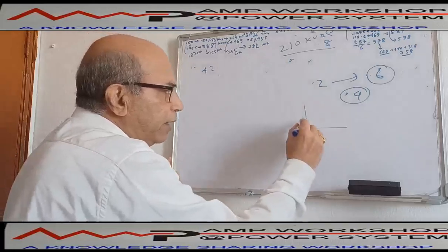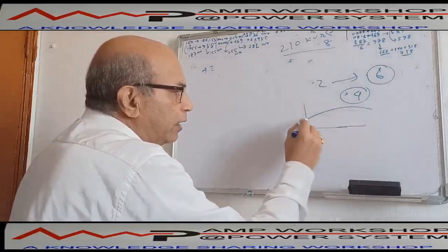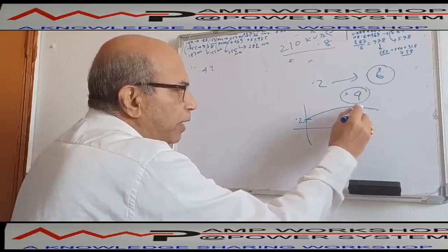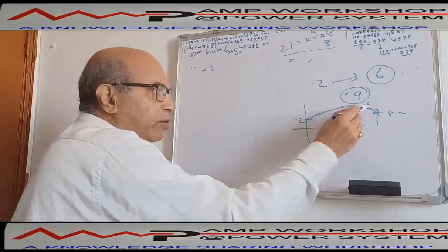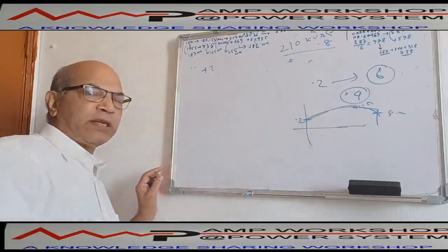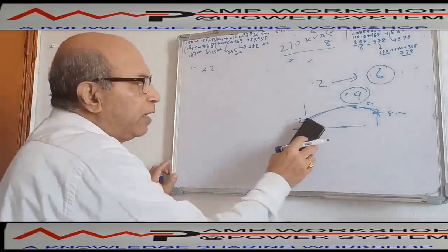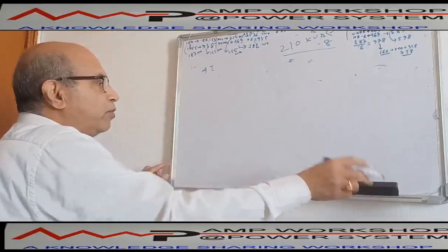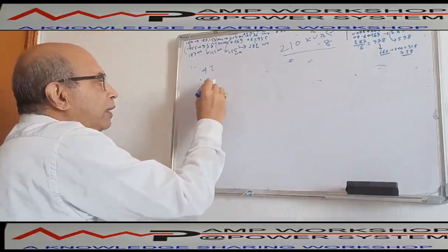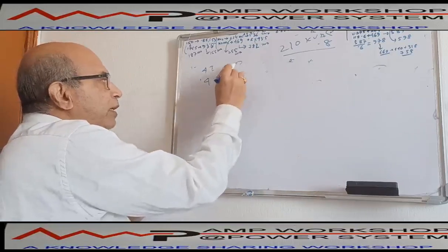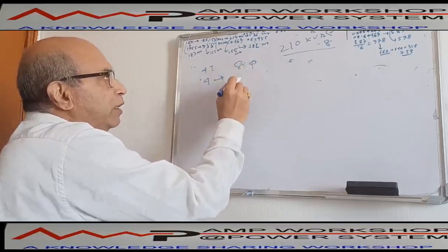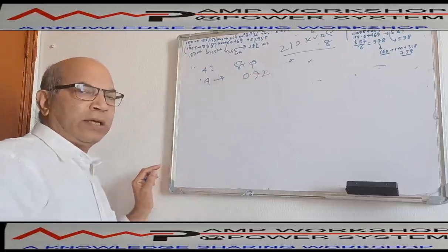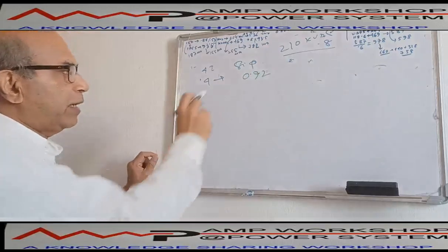during running. That means the power factor of the motor also varies like this. Initially it may be 0.2, then it goes to 0.6 maybe here. So for the starting part of the motor, we can take the average of 0.6 and 0.2, which is 0.4, as the average starting power factor of the motor. If we consider the starting power factor as 0.4, that is cos phi, then the starting sine phi will be approximately 0.92, for reactive kVAR.